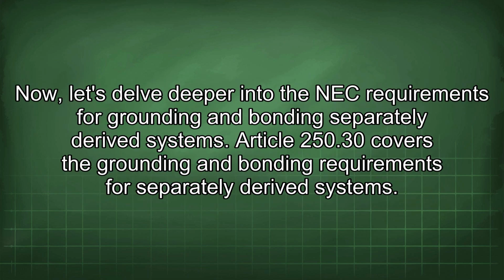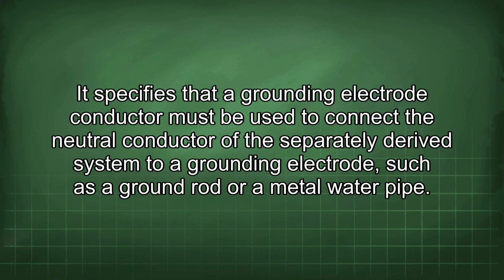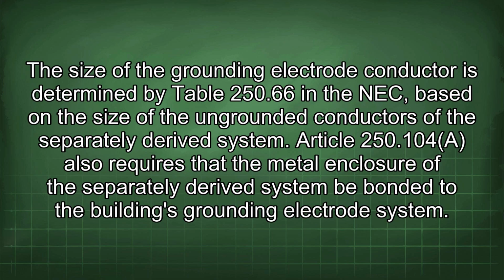Now let's delve deeper into the NEC requirements for grounding and bonding separately derived systems. Article 250.30 covers the grounding and bonding requirements for separately derived systems. It specifies that a grounding electrode conductor must be used to connect the neutral conductor of the separately derived system to a grounding electrode, such as a ground rod or a metal water pipe. The size of the grounding electrode conductor is determined by Table 250.66 in the NEC based on the size of the ungrounded conductors of the separately derived system.